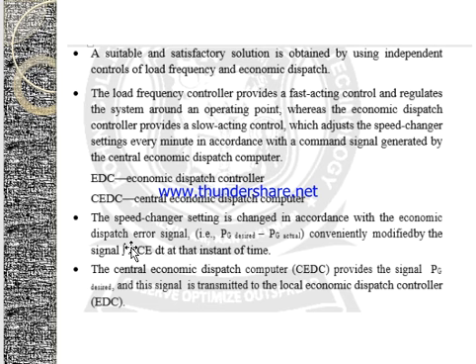The load frequency controller provides a fast acting control and regulates the system around an operating point, whereas the economic dispatch controller provides a slow acting control which adjusts the speed change settings every minute in accordance with the command signals generated by the central economic dispatch computer.